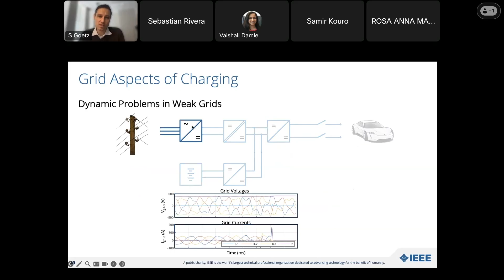Here you see a measurement of a real charger that went berserk. You see, this is what can happen already in Europe. In a grid, you measure three-phase AC. What you expect, right, is perfectly sinusoidal voltage, and what you really get is that mess here. Particularly, right, if the grid impedance is high. And you see the charger is drawing current and even influencing the voltage, and other systems might be connected to the same point of common coupling.